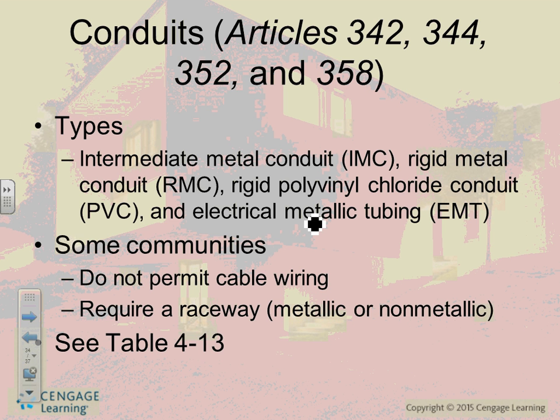Now, what happened with rigid? This is your conduit of choice, 90% of the time. Now, what happened to this and this? These are rigid metal conduit. The only difference between them, they look alike, guys, is they have a thicker shell. This one is for when Chad is mad and wants to hit it with his fist or kick it. That protects you from something like this. Can you bend that one by hand? You've got to be really strong. Can you bend it by hand? You probably can. So it's still strong.